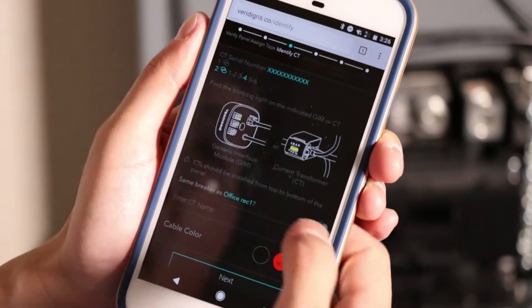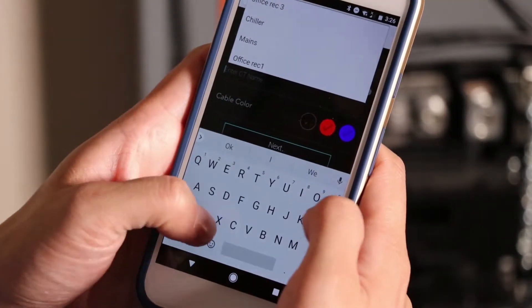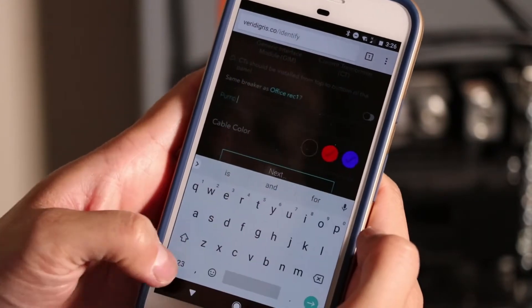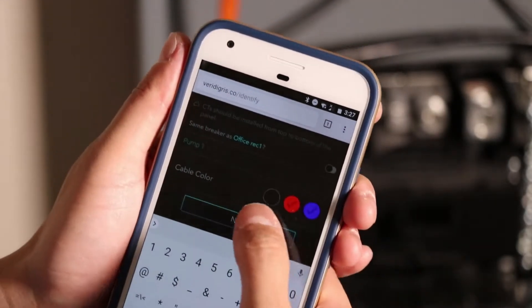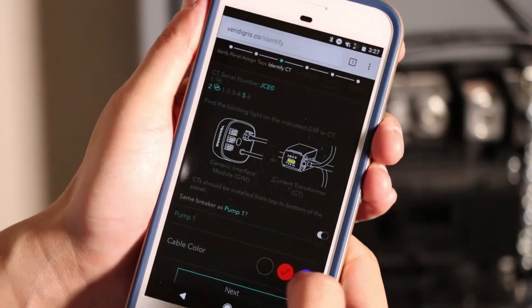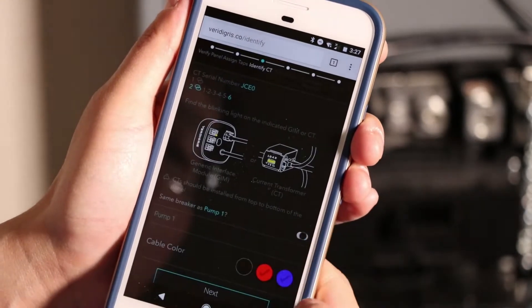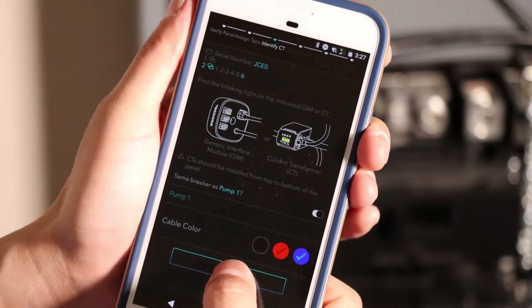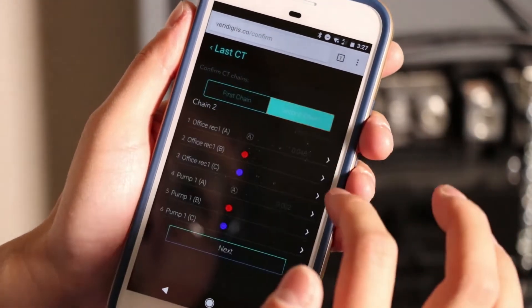Now I'm on another bank of CTs. In this case, this will be my chiller pump, so I'm going to call this 'pump one.' It's connected to a black phase. Likewise, the next is the red phase — it's pump one. Finally, the last one is connected to blue, and I'm going to complete my connections.